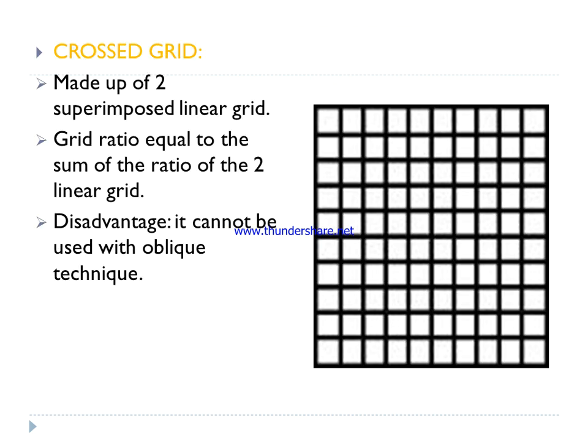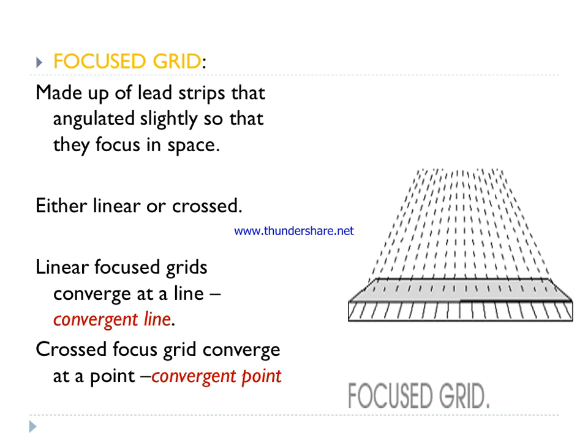In a cross grid, lead strips are superimposed on each other — present in both vertical and horizontal sections. They are superimposed, which is also described as a linear grid superimposed on another linear grid. The grid ratio of a cross grid equals the sum of the ratios of the two linear grids. Cross grids cannot be used with oblique techniques.